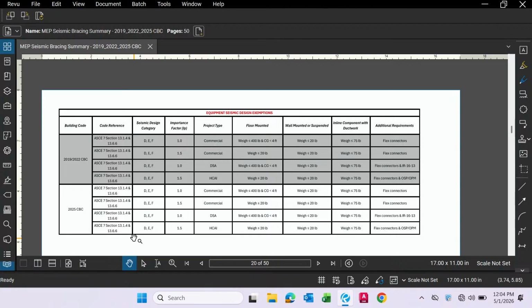When it comes to seismic bracing of equipment, the code has certain exemptions. If you have a commercial building with a component importance factor of 1.0, and the equipment weighs 400 pounds or less, you don't have to provide seismic calculations for it. There's also a requirement that the center of gravity of the equipment be less than 4 feet. You don't want a 300-pound water tank 6 feet up there without anchoring it down and without seismic design. So anything less than 400 pounds with a CG less than 4 feet doesn't require seismic calculations, but you still have to anchor it down and make a positive attachment to the ground.